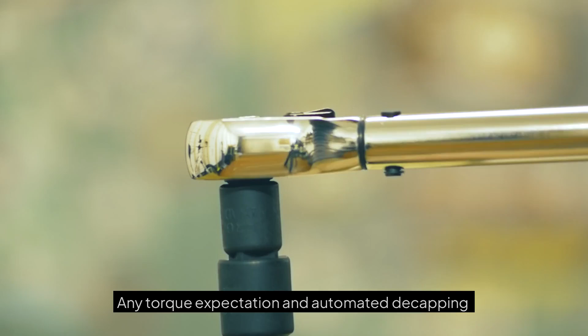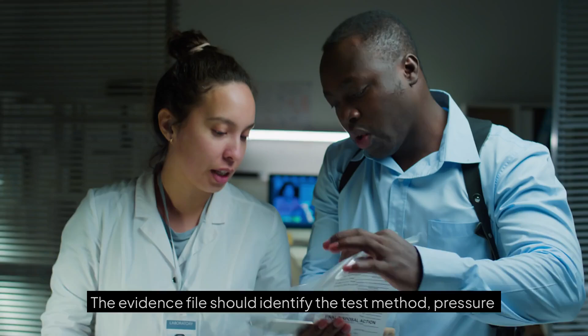Temperature transitions deserve particular attention. Movement between storage, workstations, scanners, transport containers, and analytical equipment can affect frost, grip, code visibility, and cap operation. Testing should represent the longest likely handling sequence and identify when the code is scanned and when the closure is challenged. Leak resistance claims are useful only when their boundaries are clear.